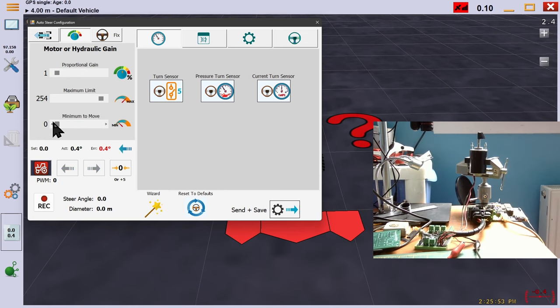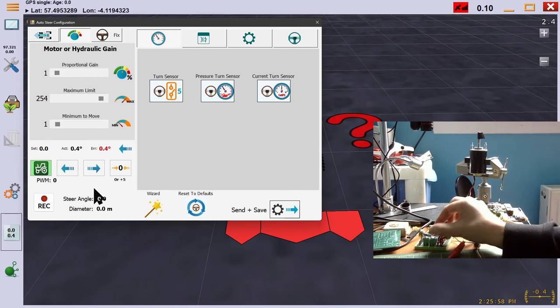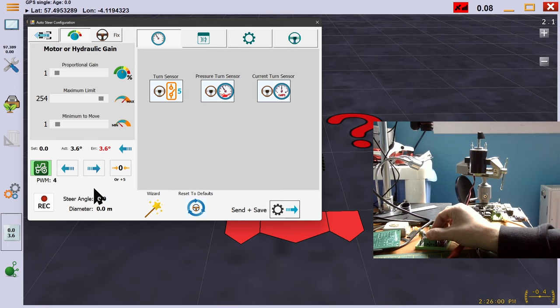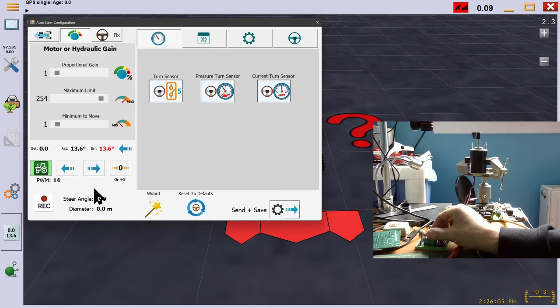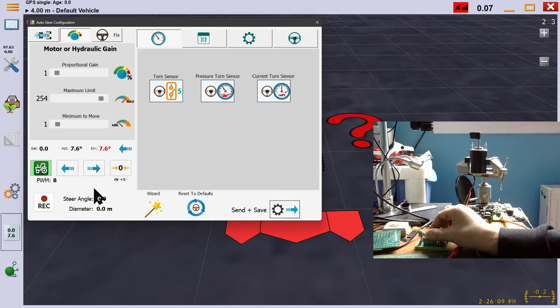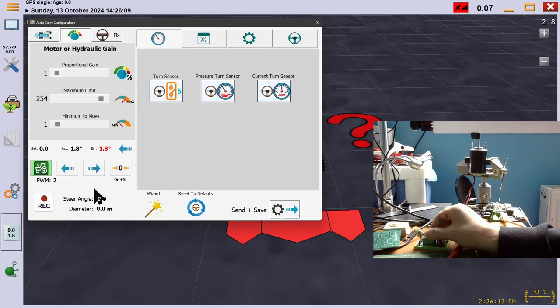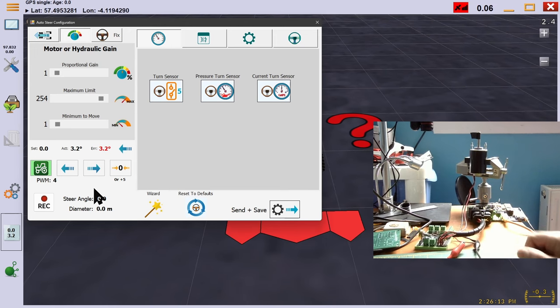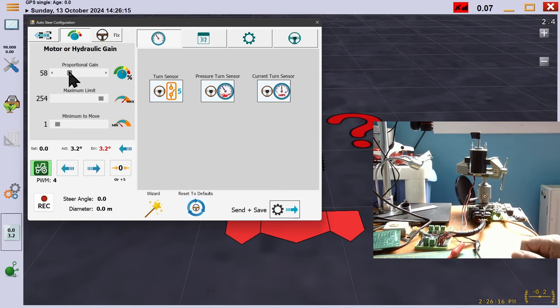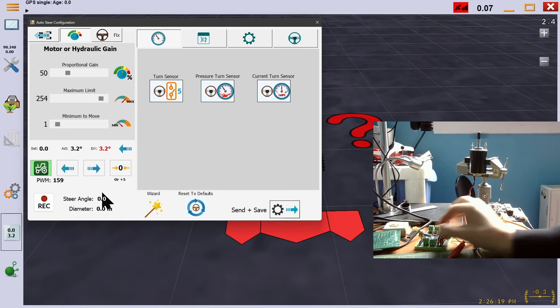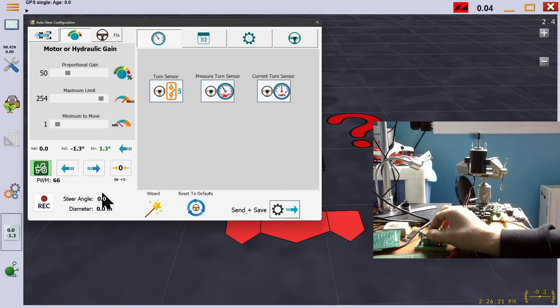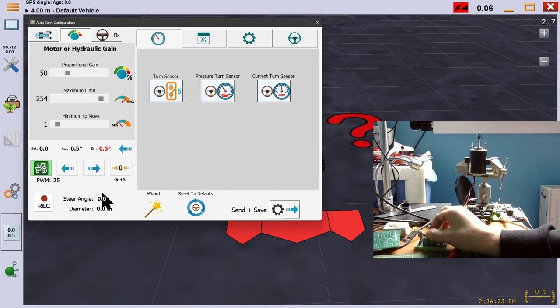And if we set minimum too low, then the error has to build up before the initial friction of the motor is overcome and it can start to turn. Here, increasing the proportional gain to compensate would be the wrong thing to do as all it ensures is the steering comes in hard when it eventually arrives.